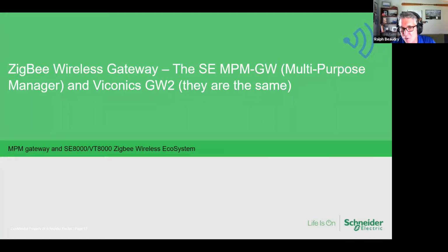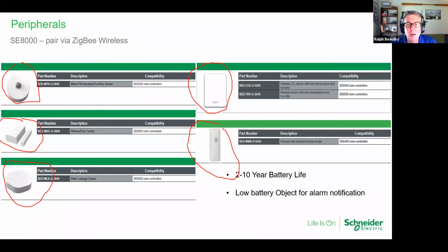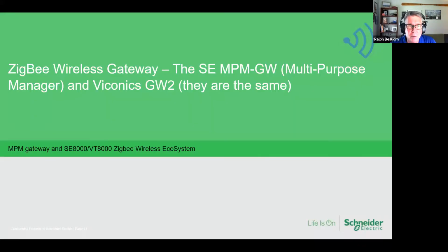Do you guys have any questions? I didn't talk about ranges, so we usually say design to 30 feet from the stat. All of the objects are BACnet objects on board. When you're talking with the ecosystem, I not only get my temperature, humidity, and whatever the device, CO2, for instance, with this guy, but I also get a low battery alarm. I didn't mention that. So battery life is 2 to 10 years, and you can set up an alarm notification to change the battery. Anything else? Any questions? No? Okay. I'll move on.